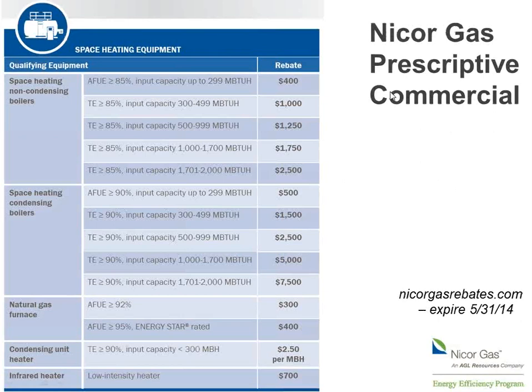All right, so looking at all the stuff listed at one time, there is a section for non-condensing boilers, or near condensing, if you want to call them that. They got to be 85% efficient. I don't know that makes a ton of sense. I mean, either you're going to put in low efficiency, entry-level 80%ers, or you're going to go with the full Monty and put in something that's 92 or 94%.